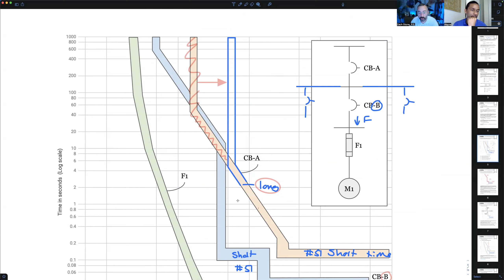So again, here's the long time trip region. We talked about tap setting. What about time delay? What does time delay do? It moves it on the vertical axis. So looking at circuit breaker A, if I increase the time delay, or time dial, for this same long time trip region, here's what it would look like.